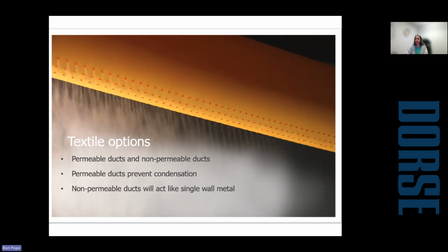There's 2 main types of material that is used for fabric duct, a permeable and a non-permeable option. Permeable duct is what we are most frequently using because it helps prevent condensation. And the way that it does that is a little bit of the air actually seeps through the surface of the fabric and creates a barrier around the duct, and that just prevents your room air from actually ever touching the surface of the fabric, thus preventing the condensation.